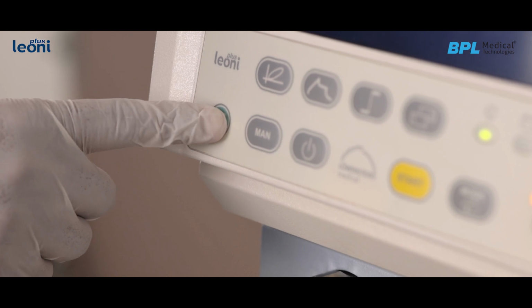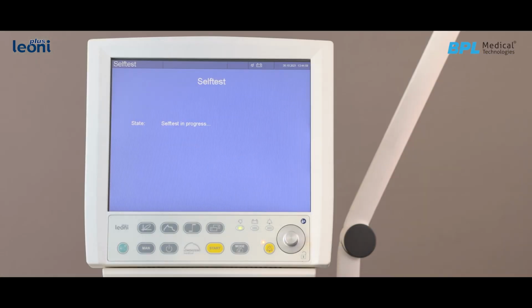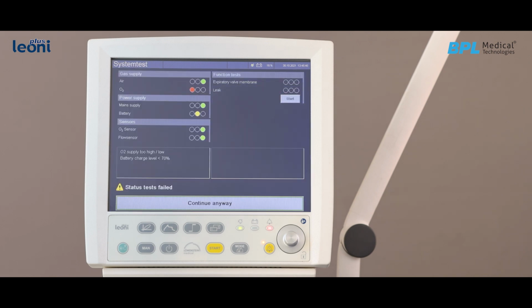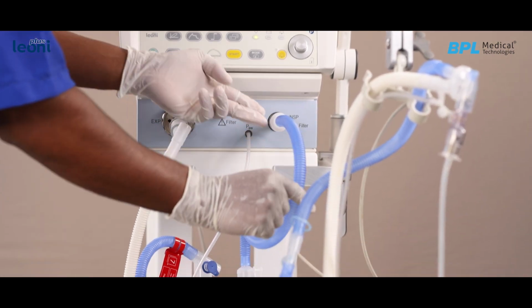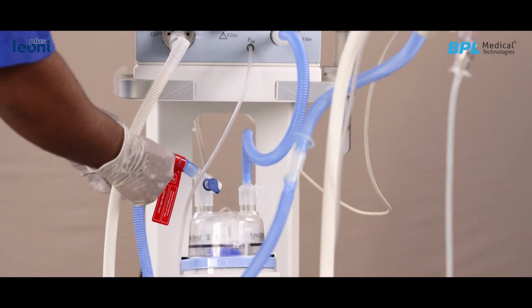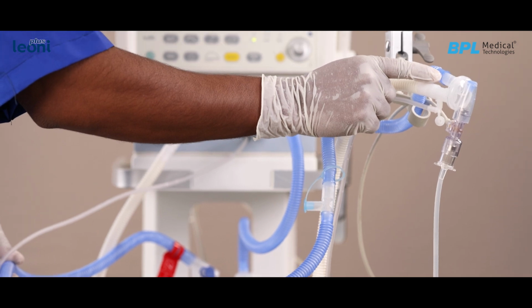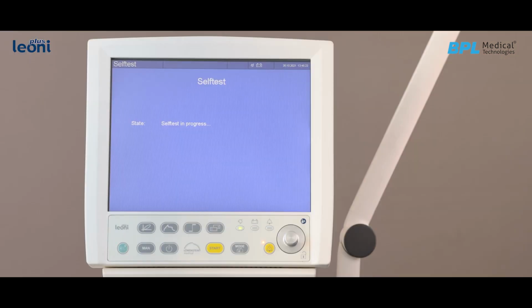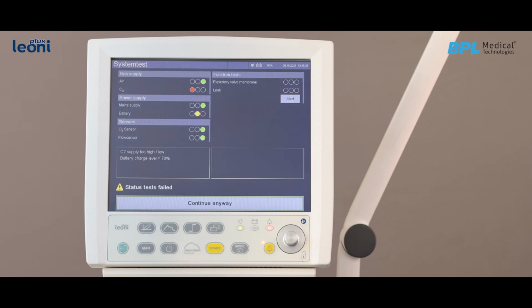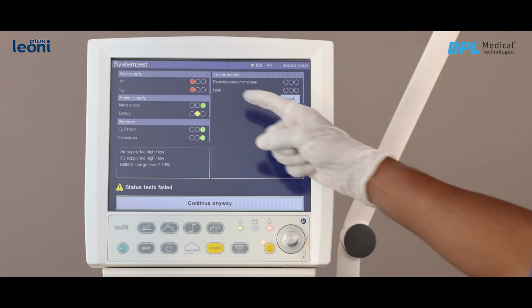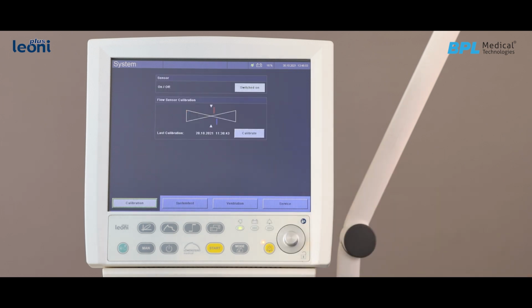Press the master control switch to switch on the device. The unit will boot up with the self-test and will show a test checklist along with a traffic light indication. With a proper assembly of breathing circuit, the machine will check for leakage, pneumatics, sensors, power supply voltages, etc. Once all the self-tests are successfully completed, the unit will enter the sensor calibration page. In case of failure of the test, press Continue Anyway to enter the calibration page.